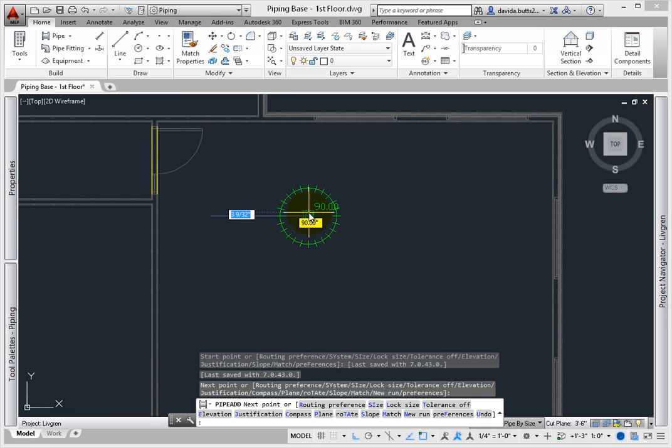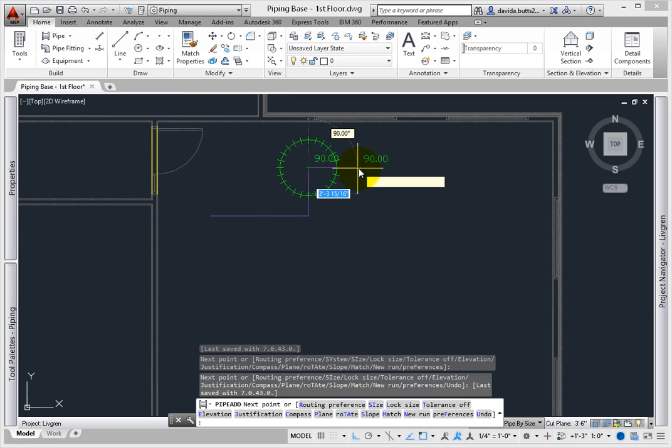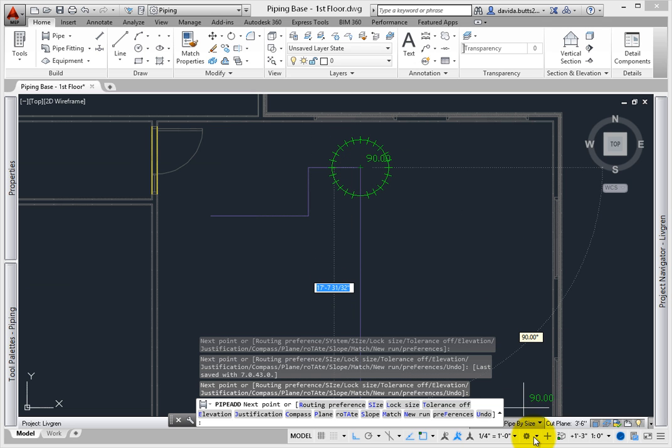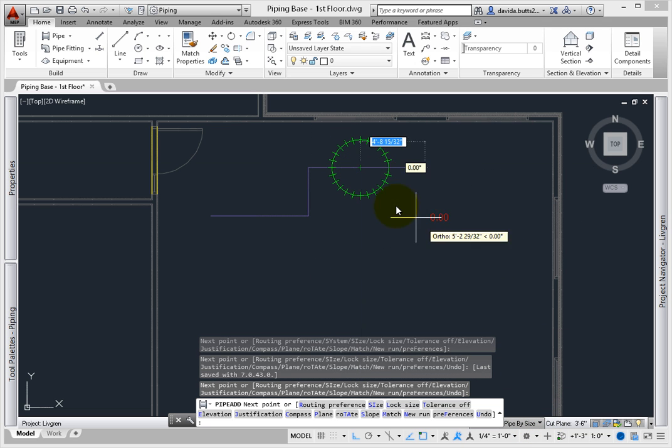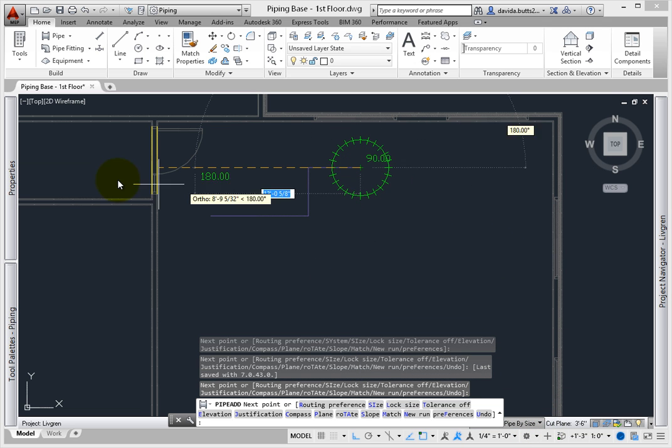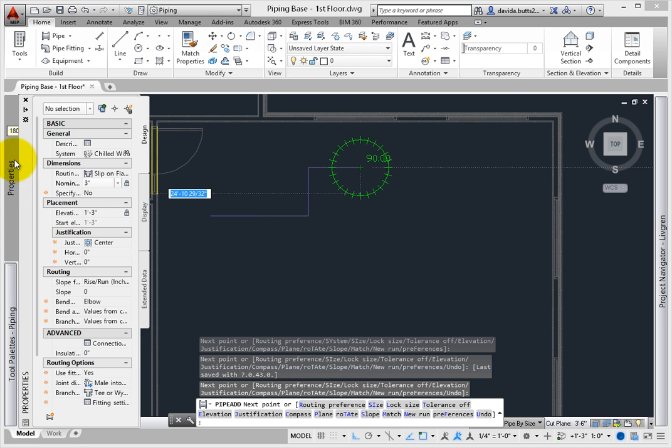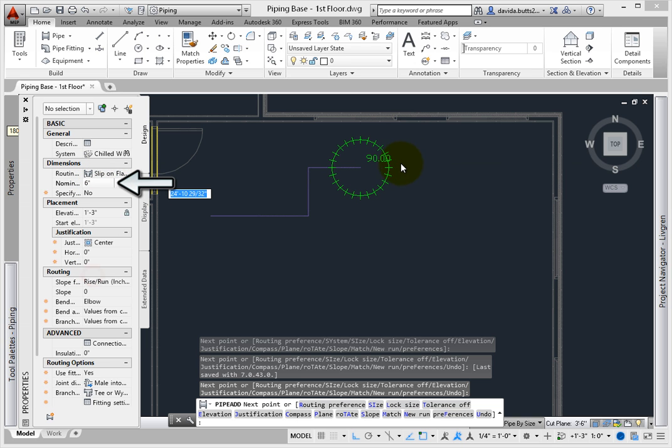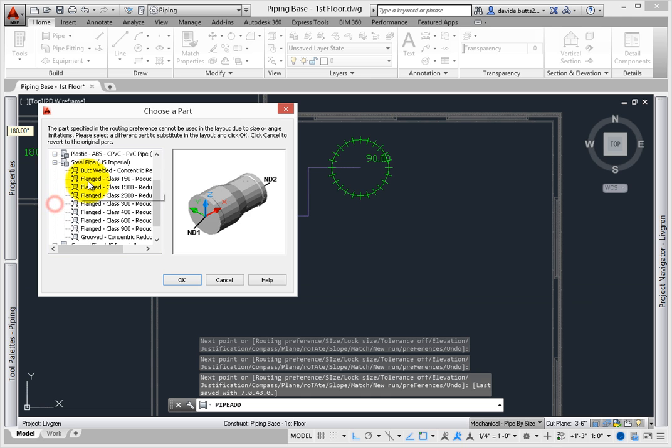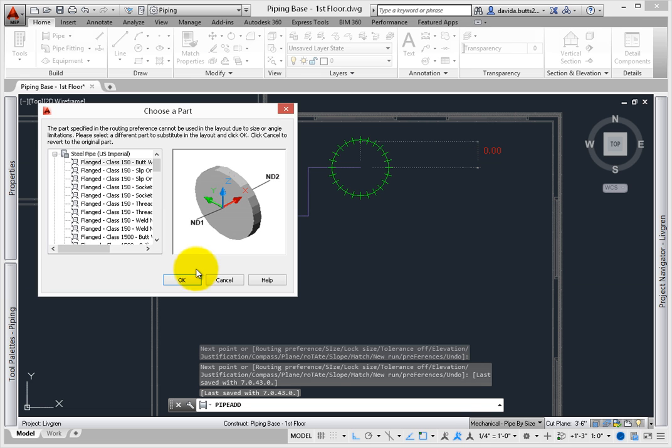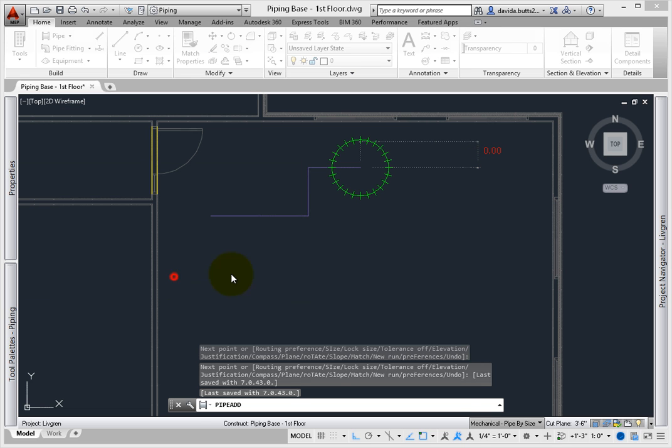It appears as a single line when the MEP design, mechanical, or pipe by size display configuration are set current. Change the size to 6 inches, pick a reducer, and then draw another segment to continue. See how the small pipe is single line, but the large pipe is double line. This helps keep the construction documents clear.